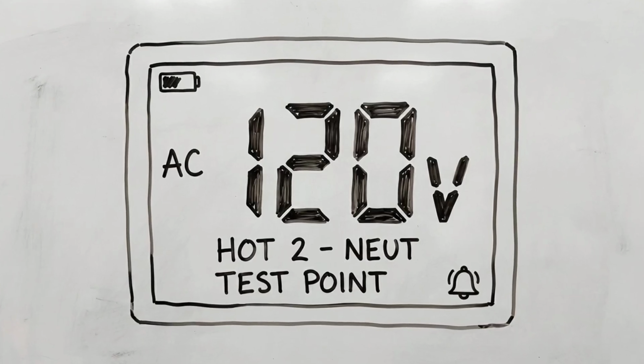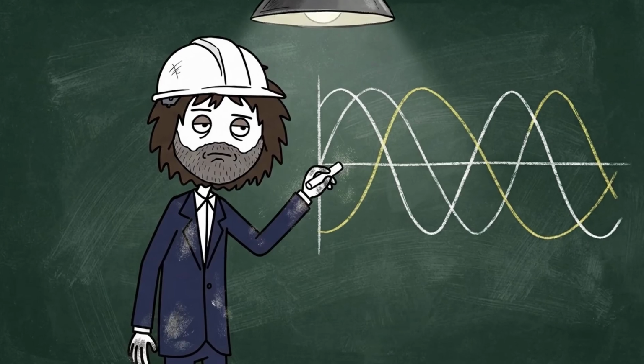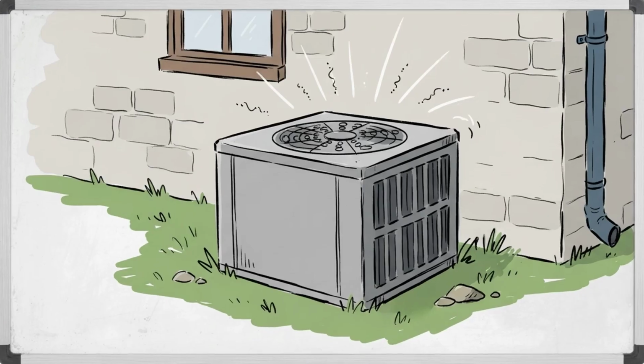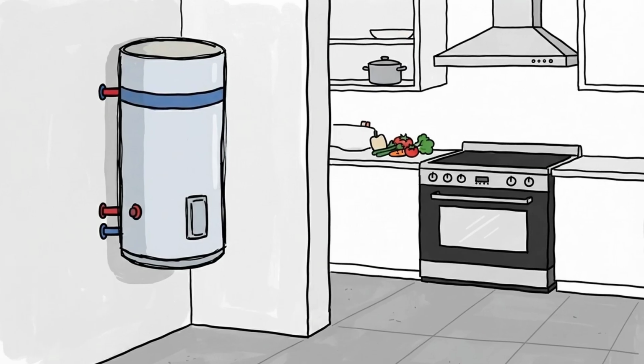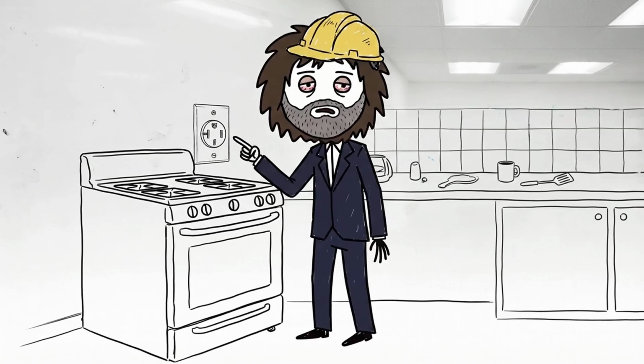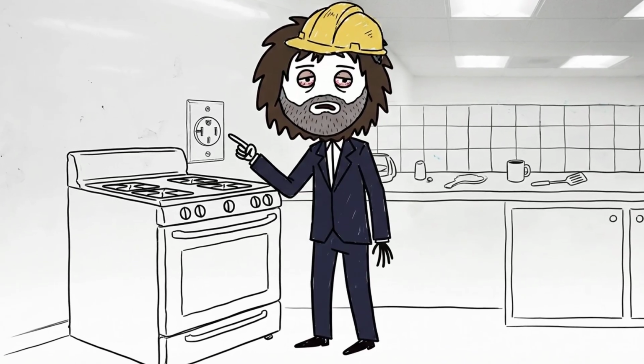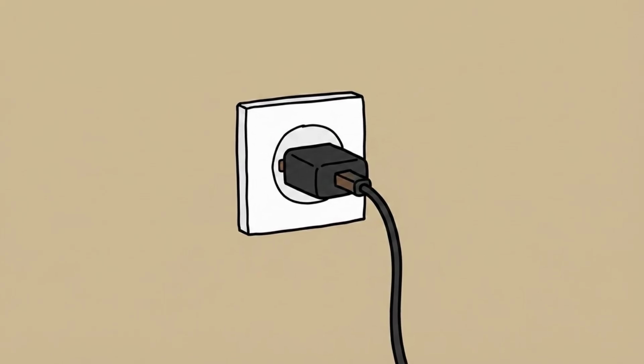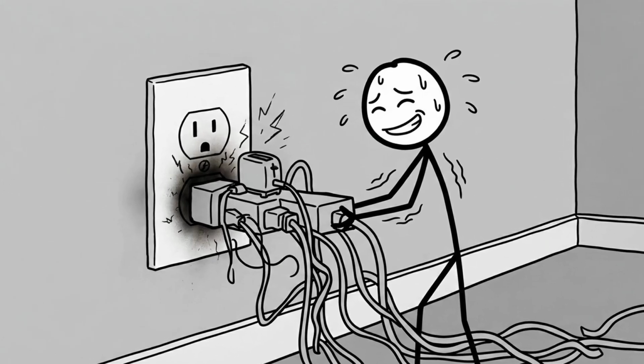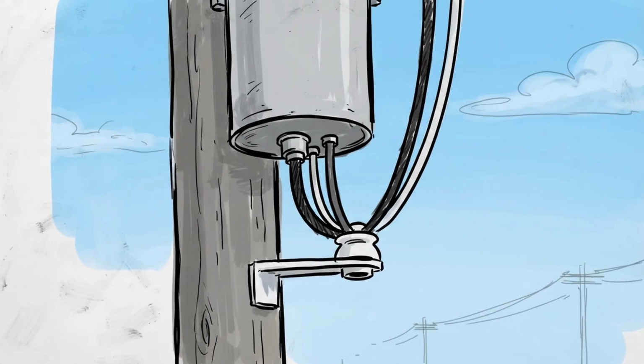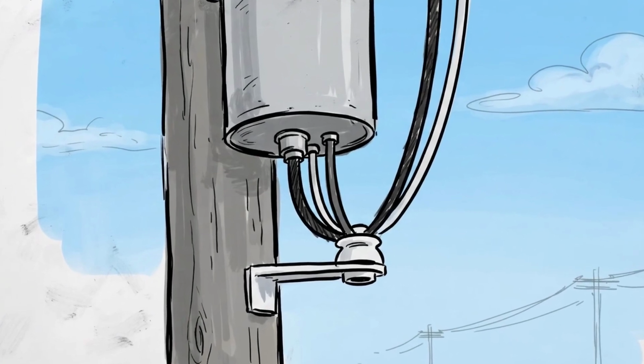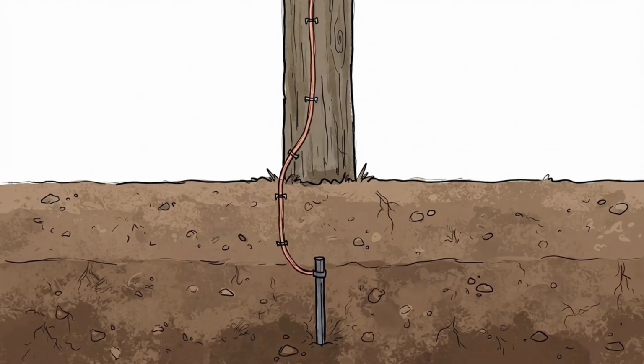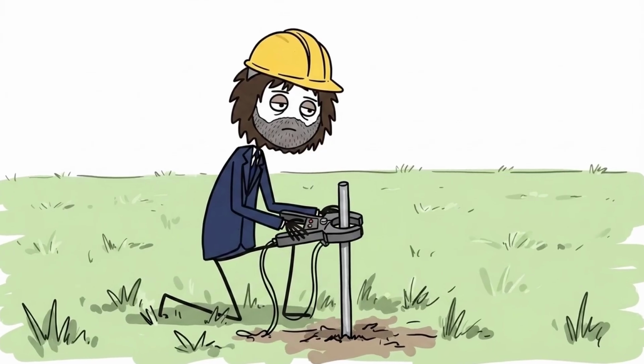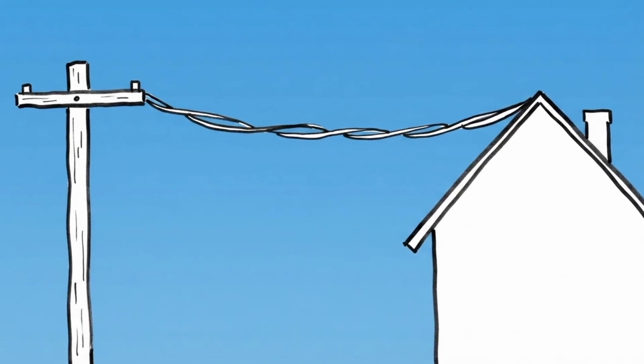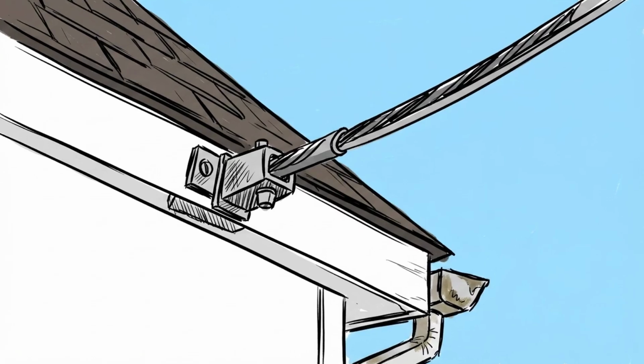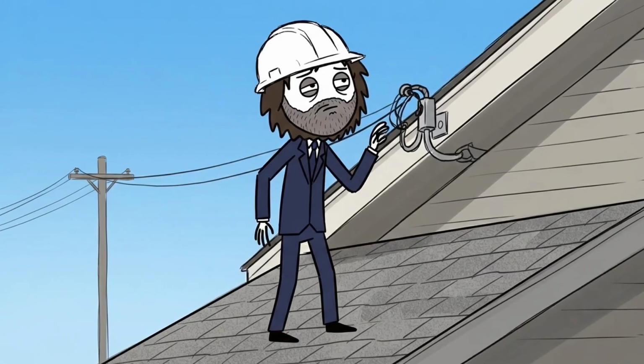But instead of just outputting 2 simple wires, the transformer's secondary coil is tapped right in the dead center, creating a center-tapped neutral wire. This split-phase design is why North American homes have access to 2 distinct power levels from the exact same transformer. Measuring the electrical pressure from one outside hot leg to the other hot leg gives you a full 240 volts, which is what your heavy-duty appliances like your central heat pump, electric water heater, oven, and clothes dryer consume. But measuring from either individual hot leg to that center-tapped neutral gives you exactly 120 volts, which powers all your standard wall outlets, lamps, computers, and phone chargers.